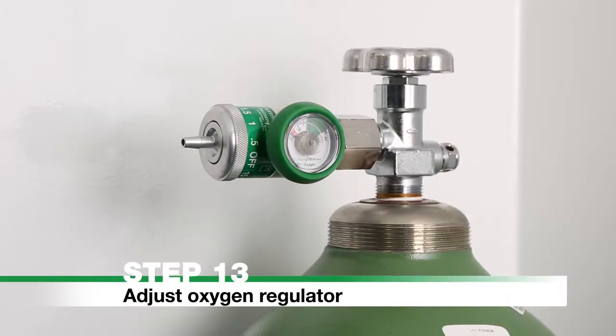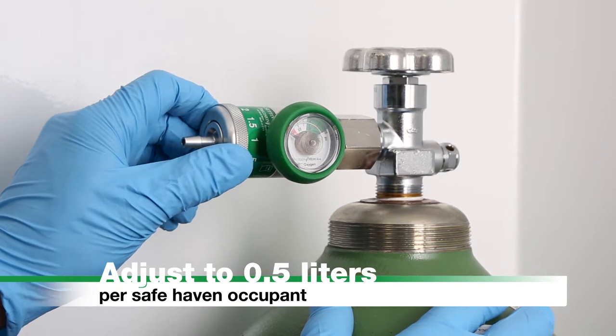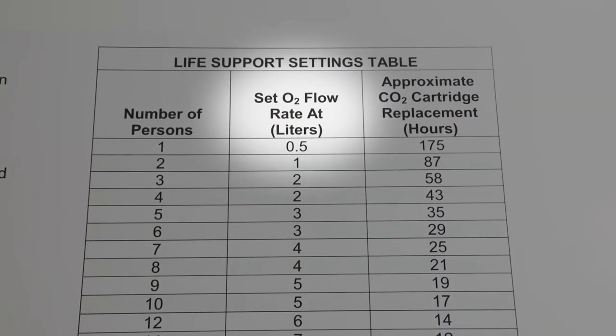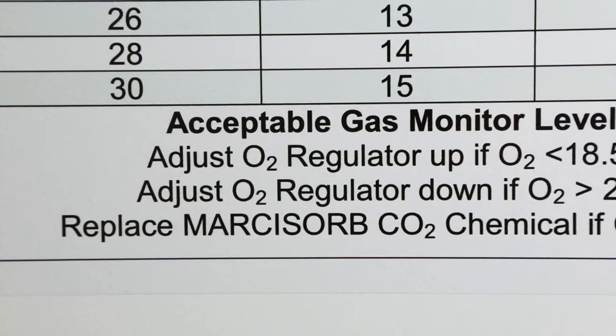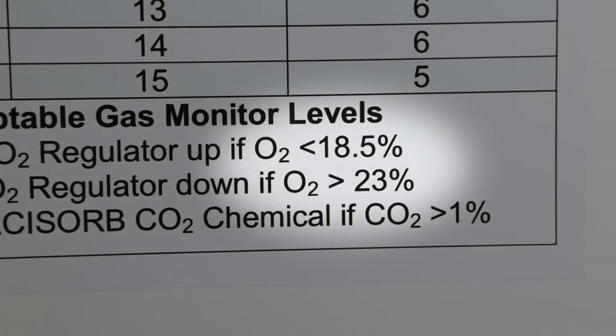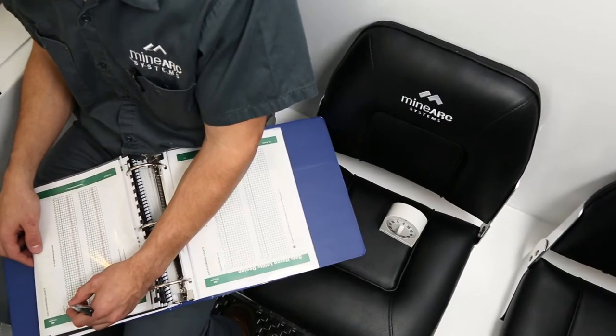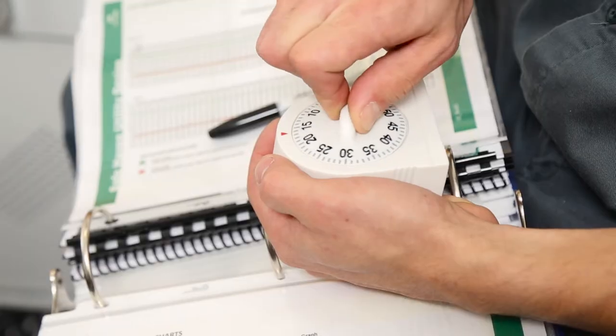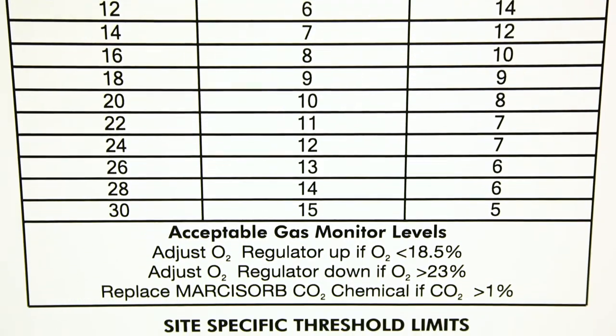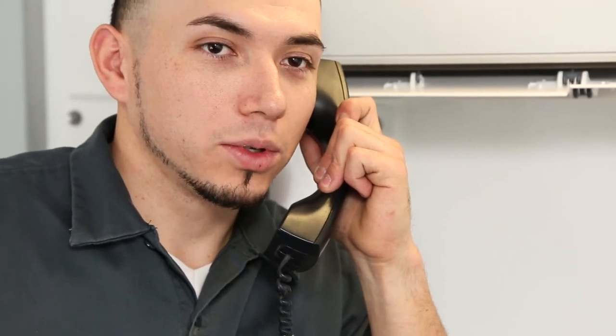Step 13: Adjust Oxygen Regulator. Adjust the oxygen regulator to 0.5 liters per safe haven occupant, rounding up to the nearest flow rate marked on the regulator. For further information on oxygen flow rates, refer to the life support settings table on the safe haven wall. If an automated oxygen delivery system is installed, the oxygen concentration will automatically be maintained between 18.5% and 23%. Remove PPE and store underneath seats. Remain calm and record gas levels hourly on the gas level recording charts located at the rear of the photographic operating procedures. A marker and timer can be found in the storage container. If internal air reaches the site-specific threshold limits specified on the life support settings table, contact the emergency incident commander for further instructions.